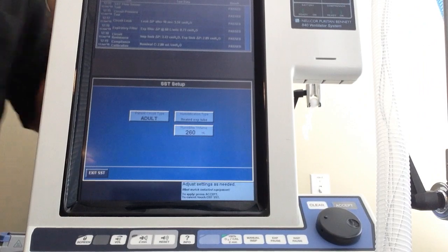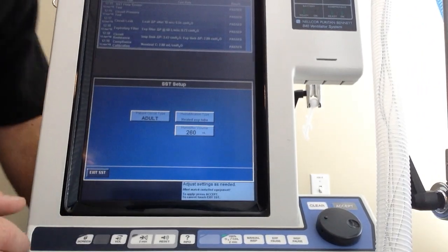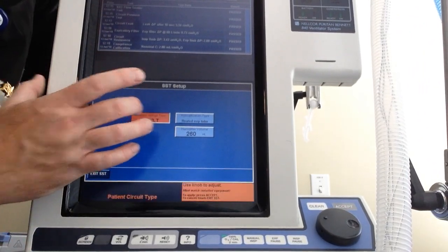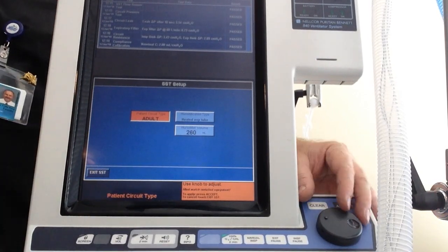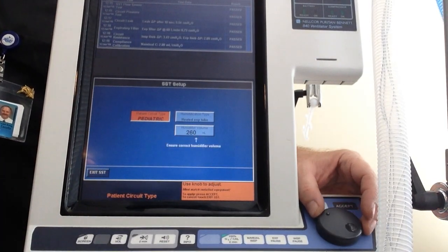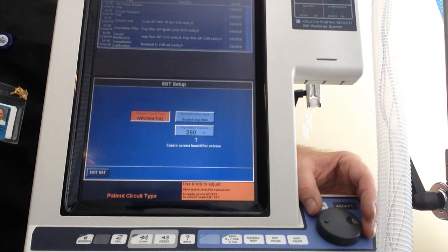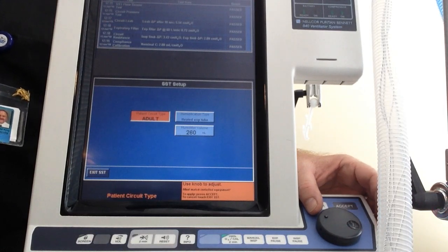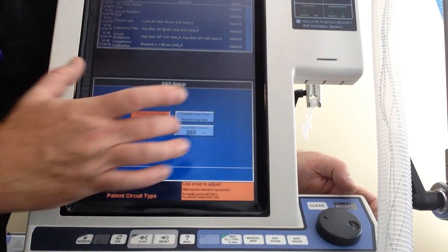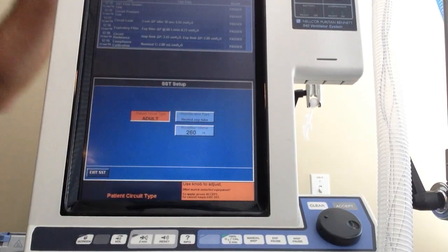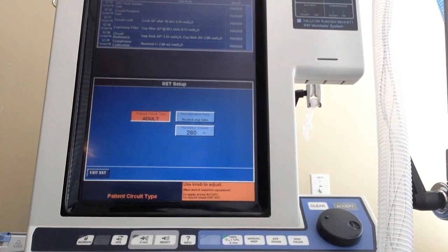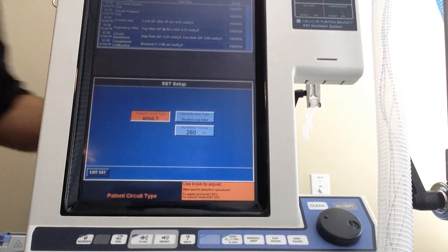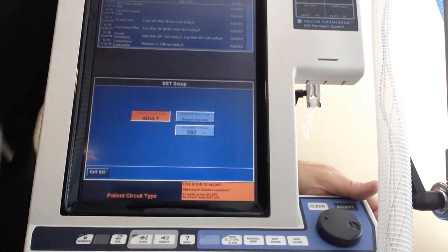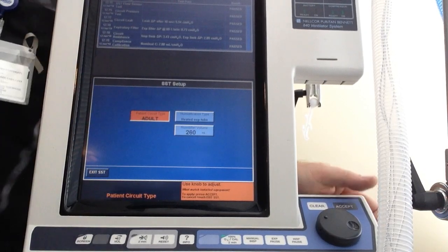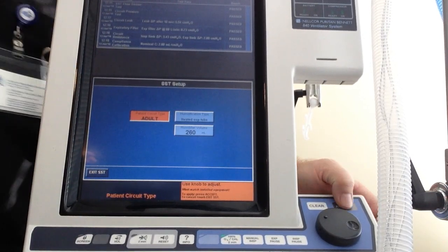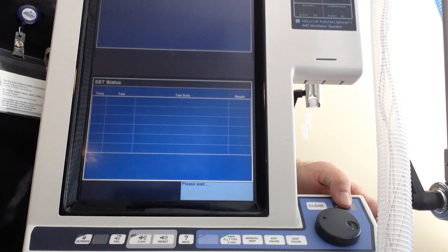I'm now into my test mode. What type of patient am I going to have? I'm going to have an adult. If I wish to change it, I could change it with the dial. We're going to stick with adult. Whenever I'm happy with my choices, I just hit accept. We have a heated expiratory tube, yes, and I'm happy with all that, and the humidifier size is the appropriate size. I'm going to hit accept.